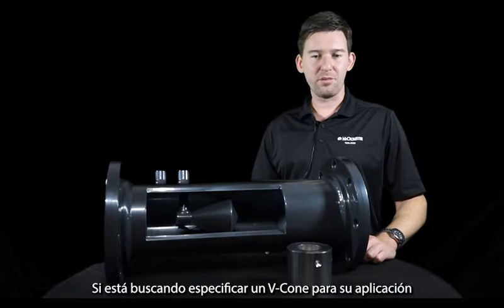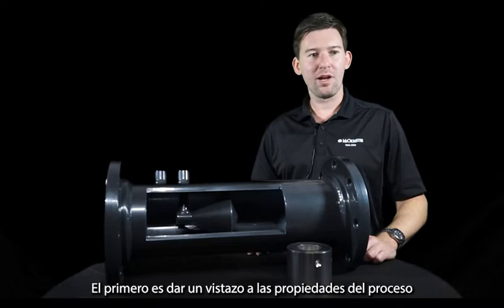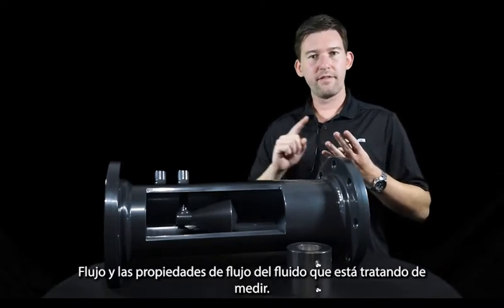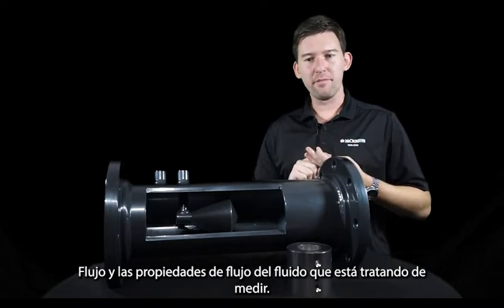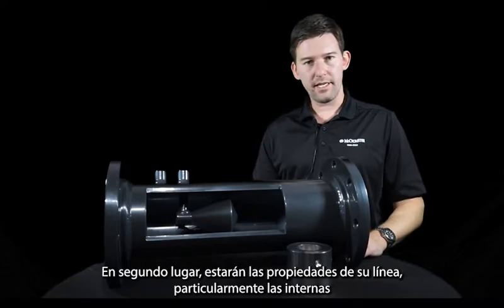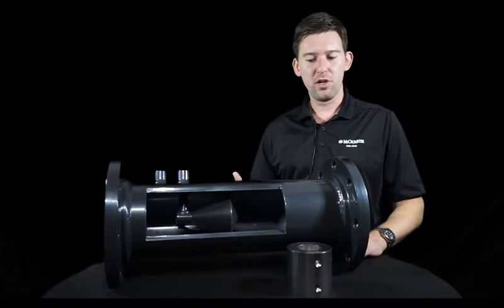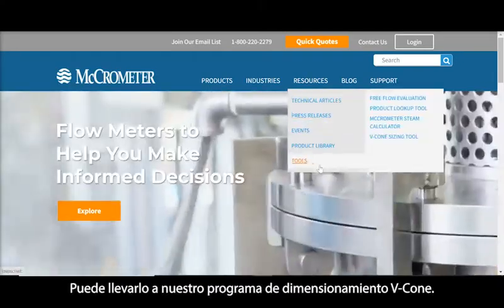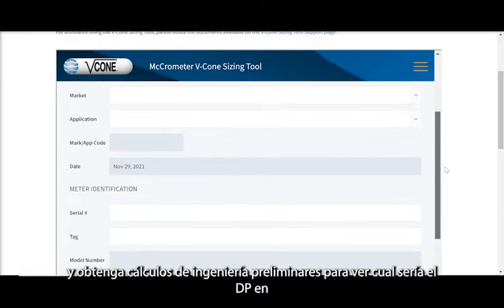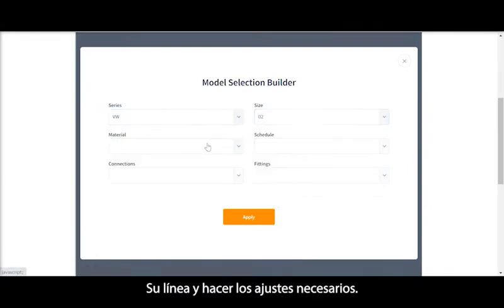If you're looking to specify a V-Cone for your application, you'll need to gather a few pieces of information before we get started. First, look at process properties — particularly pressure, temperature, flow rate, and the fluid properties of the fluid you're trying to measure. Second are the properties of your line, particularly the internal diameter, the pipe schedule, and the flange class pressure rating. Once you've gathered all this information, you can take it to our V-Cone sizing program, where you can input the information and get preliminary engineering calculations to see what the DP in your line might be and make adjustments as necessary.